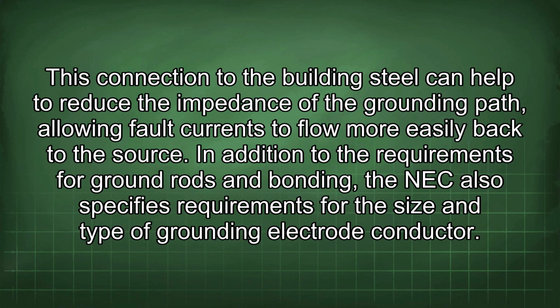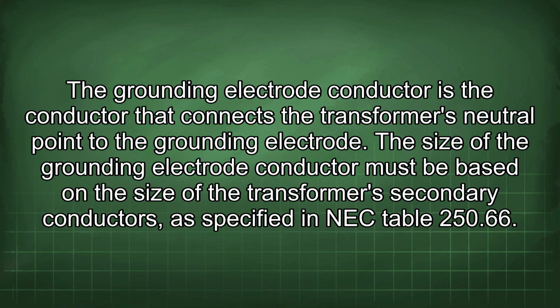This connection to the building steel can help to reduce the impedance of the grounding path, allowing fault currents to flow more easily back to the source. In addition to the requirements for ground rods and bonding, the NEC also specifies requirements for the size and type of grounding electrode conductor. The grounding electrode conductor is a conductor that connects the transformer's neutral point to the grounding electrode.